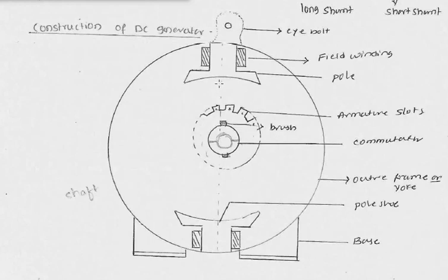The armature is the rotating part. It has slots on the outer periphery. The armature is a cylindrical structure made up of silicon steel material using thin laminations — all those thin laminations are stacked together to form the cylindrical structure. On the outer periphery we have the slots, and inside the slots we place the armature winding. This whole armature is mounted on a shaft.